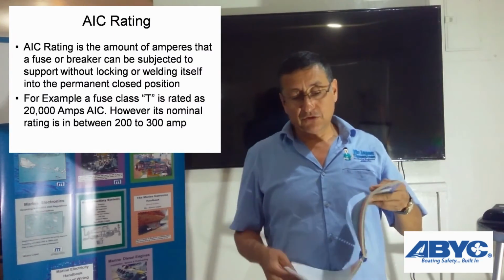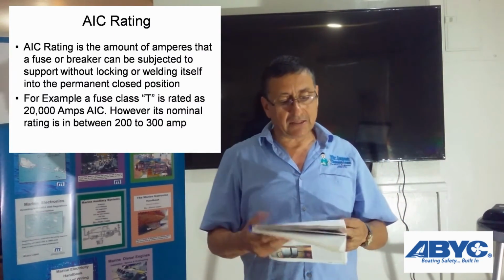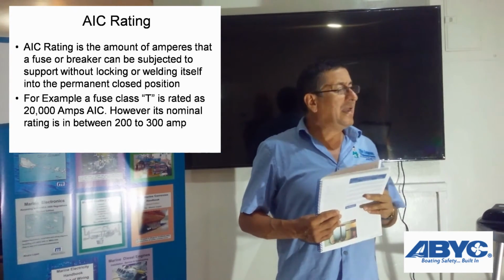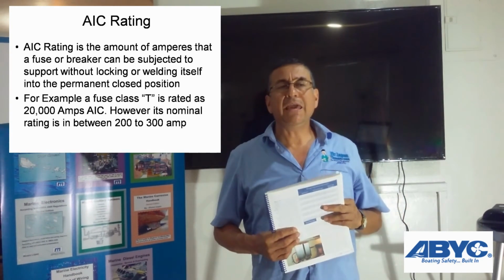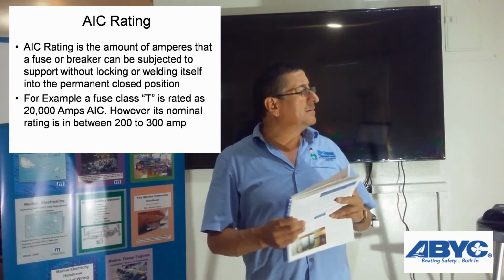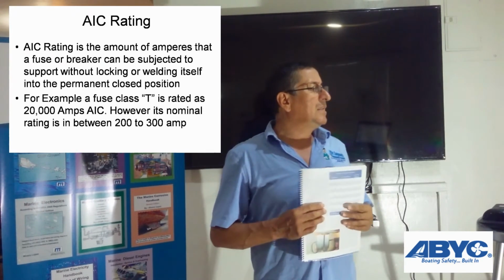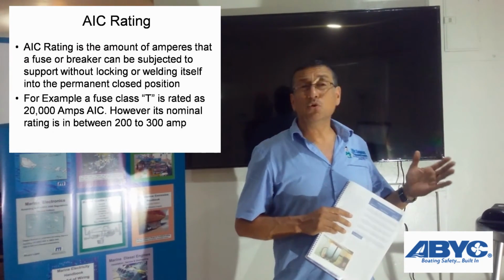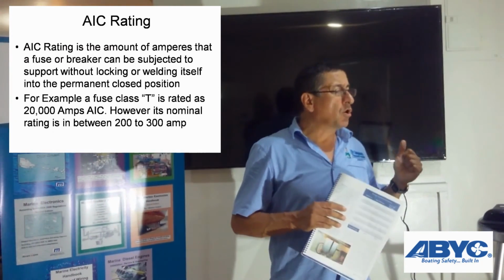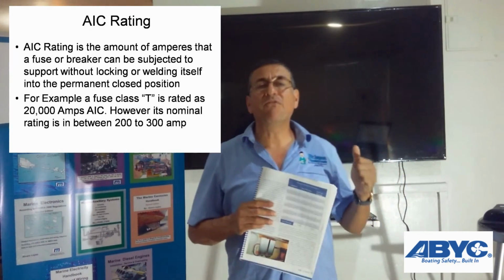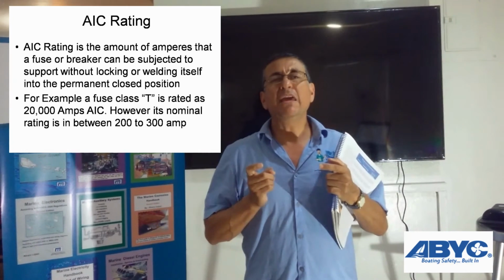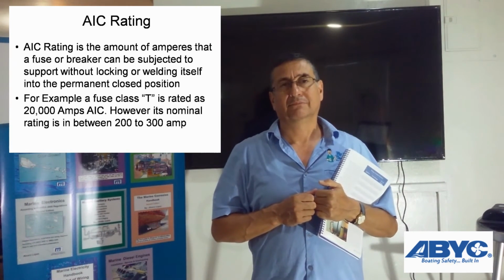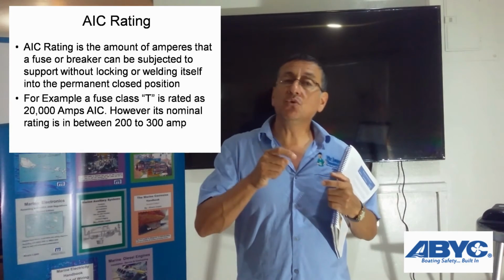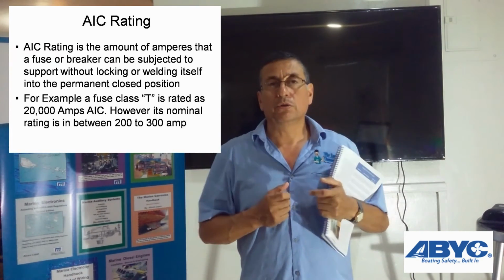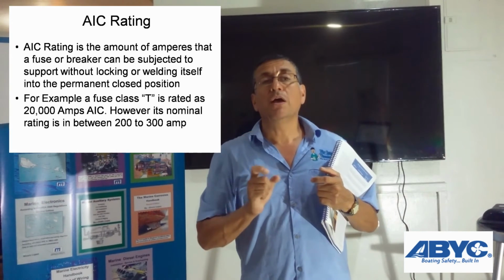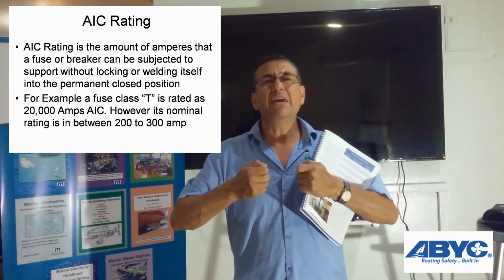Another important recommendation that I found in the ABYC study guide is in relation to the AIC rating. This is basically it: the AIC rating is the amount of amps that a fuse or breaker can support when the contacts are closed before those contacts are welded together.